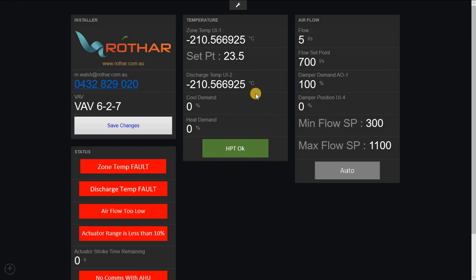This program requires a discharge sensor, which is the temperature sensor installed after the heater. It also requires the feedback to be wired in so that we can test the functionality of that actuator. We have a block called our daily test, which I believe there's also a video for, that once a day will force the actuator to restroke, exercising the damper and also confirming the operational range of the actuator. If the range isn't wide enough as preset in the block, then it will generate this alarm.